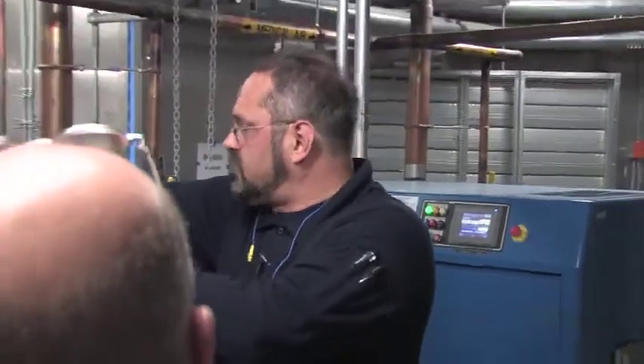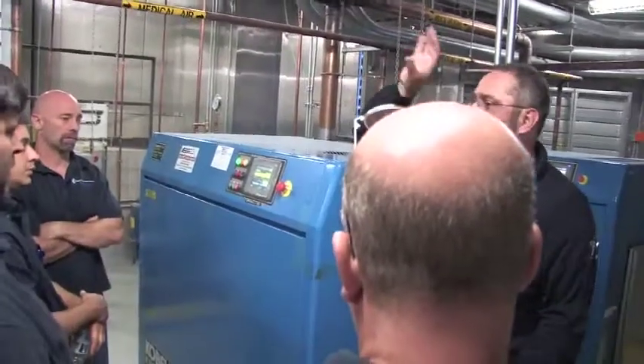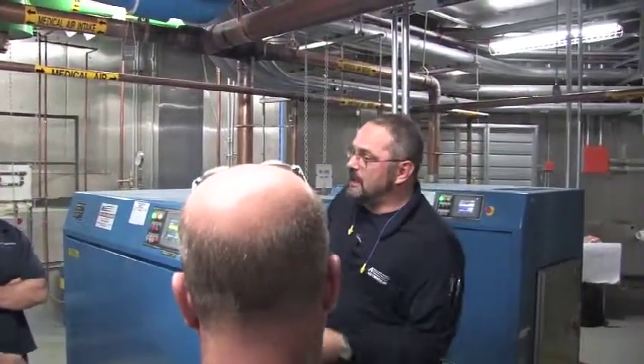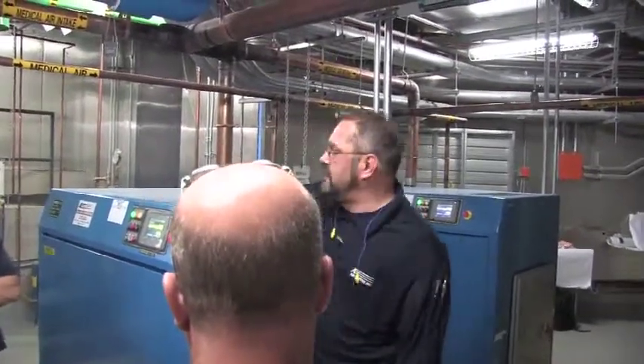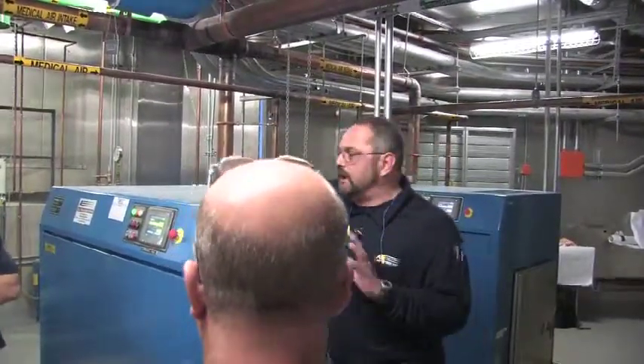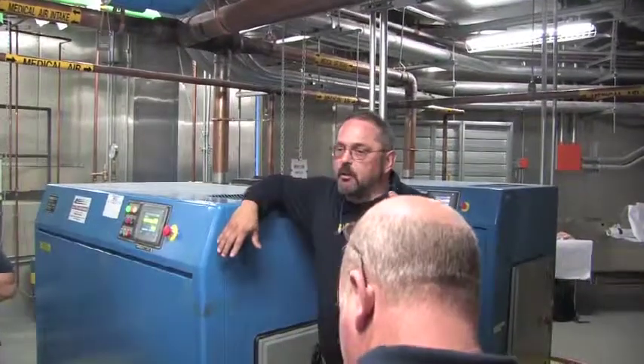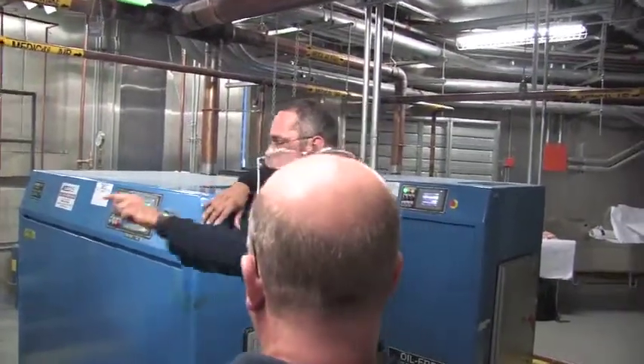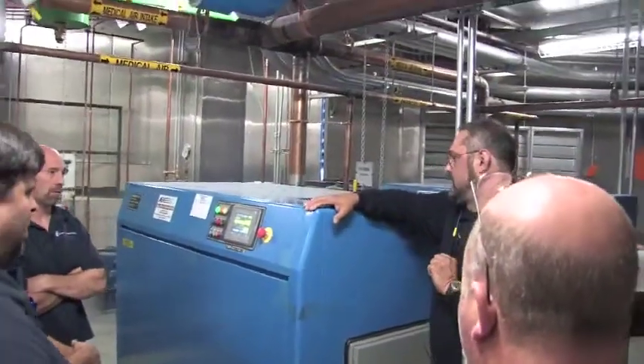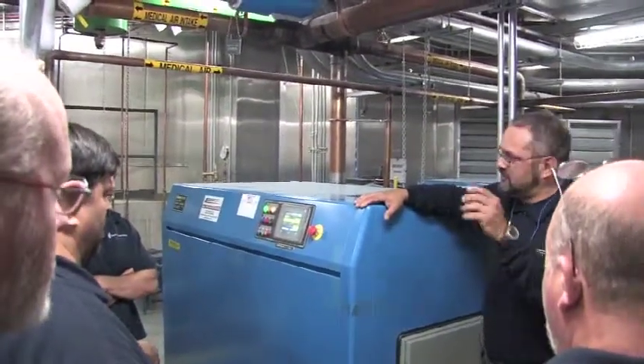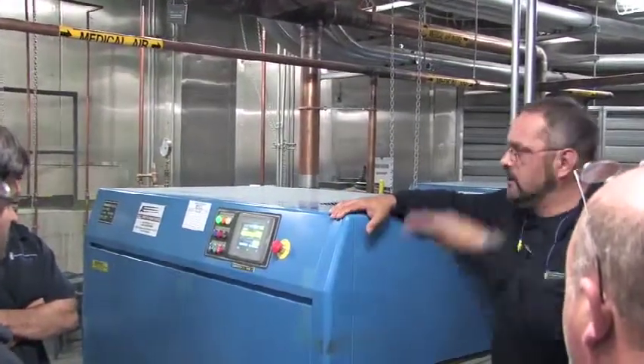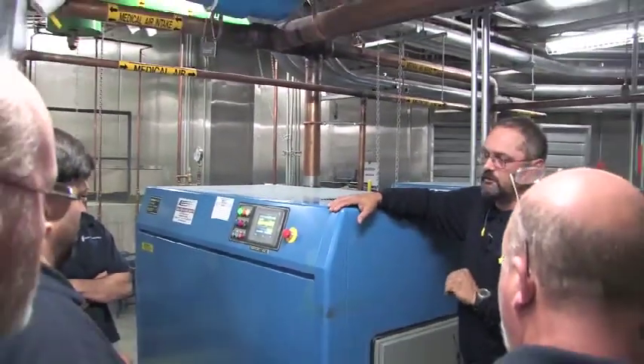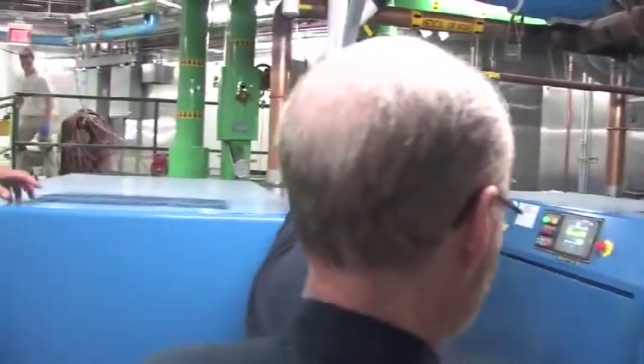But what you really want to think of is that's the master unit. That's got the sequencer in it. Just think of this one as sitting here with the sequencer box mounted right to it. The only difference is it's not a separate box. It's actually just another set of screens in the existing controller. So that's the master unit. The one thing you want to bear in mind is if you shut this unit off to work on it, it's the master and it's got the sequencer in it. So when you kill power to this unit, you're killing that sequencer. So if you're going to work on the master unit, flip these into local before you shut it off.